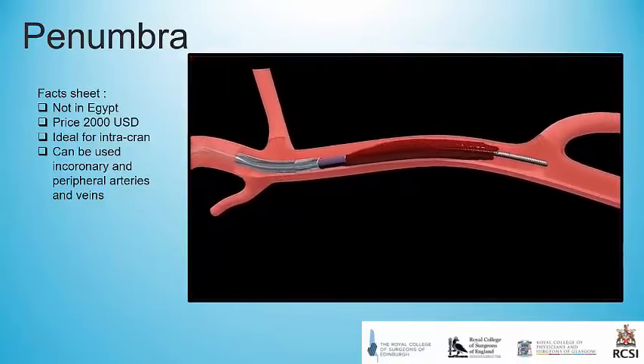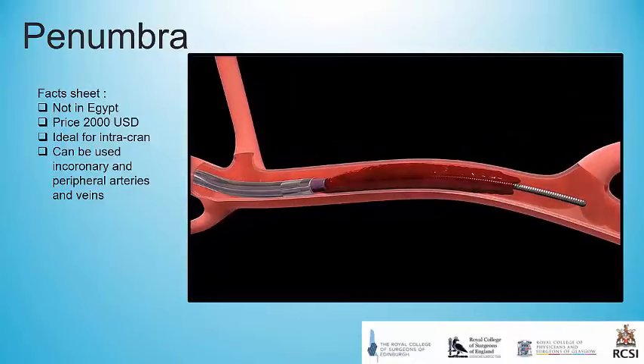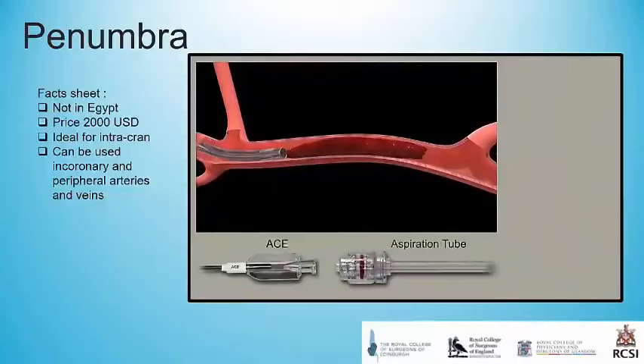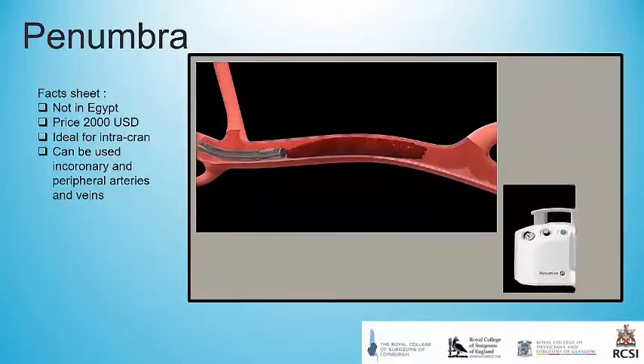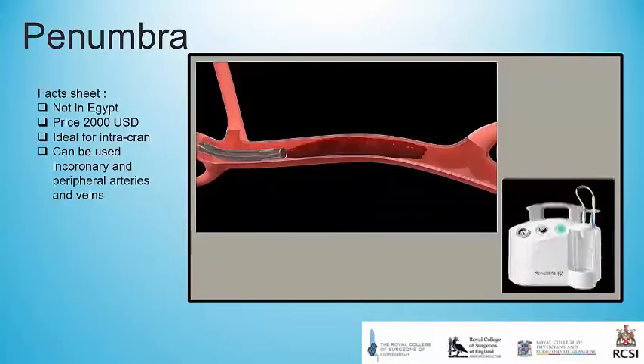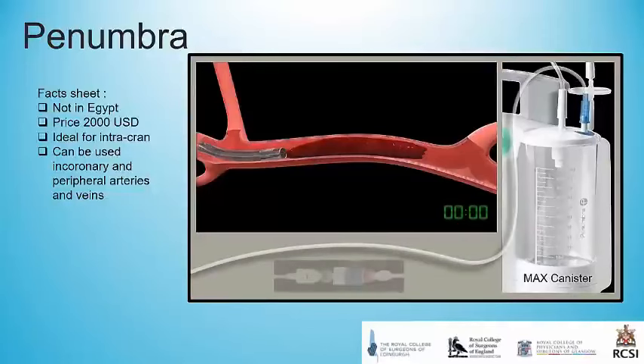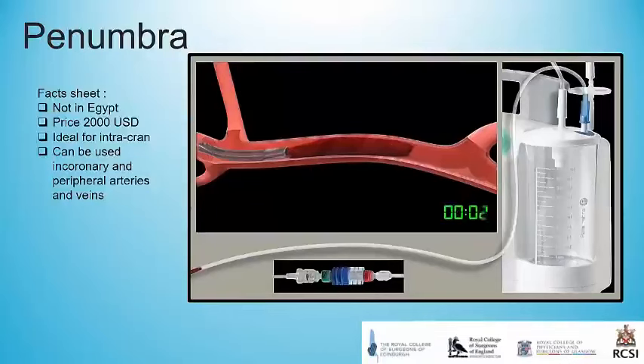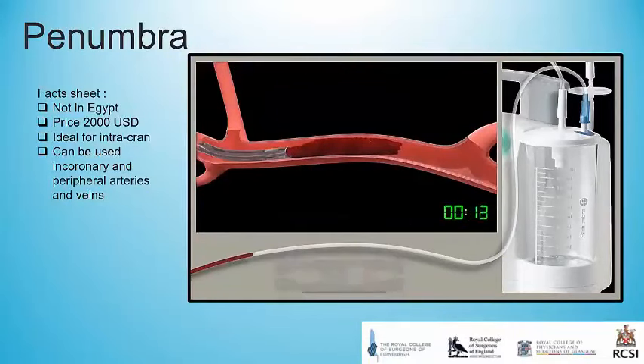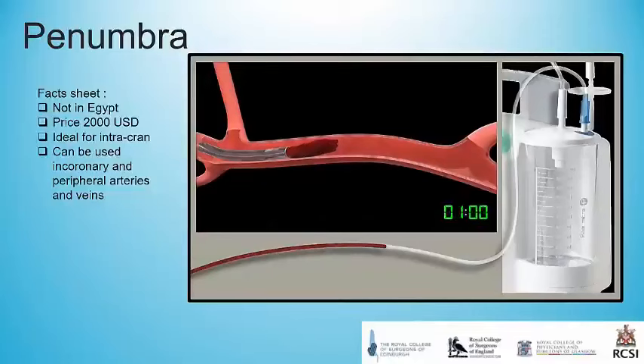It's a computerized demonstration of how the system works. You cross the fresh thrombus with the guide wire, a 0.014 specific guide wire with the Penumbra device. Then you put the device at the proximal end of the thrombus, and then you connect it to the aspiration tube, and then you start suction. This is a very, very soft suction pump, and it has FDA approval to be used intracranial and in lower limb arteries and lower limb veins. And this is the demonstration of how the technique works and how it takes the thrombus out. And after the thrombus is retrieved into the tubing, then you will restore the blood flow. And it's ideal for intracerebral circulation.